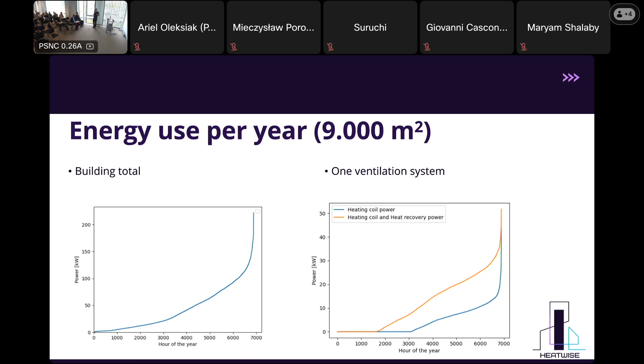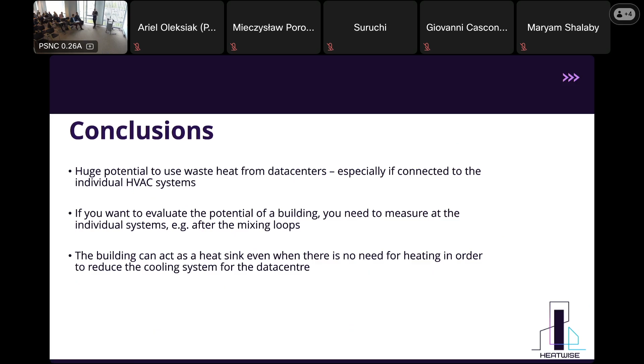If you want to evaluate the potential of a building, you need to measure at the individual systems, after the mixing loop, if you want really low temperatures. Try to investigate the building as a heat sink even when there's no need for heating, in order to reduce the cost for the cooling system of the data center. The more you can use the building, the less you have to pay for cooling your data center.